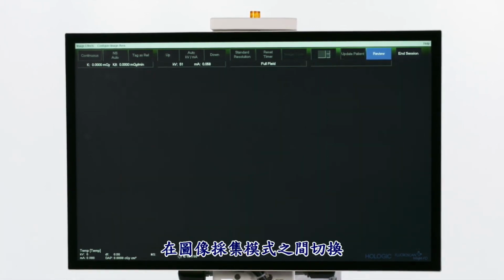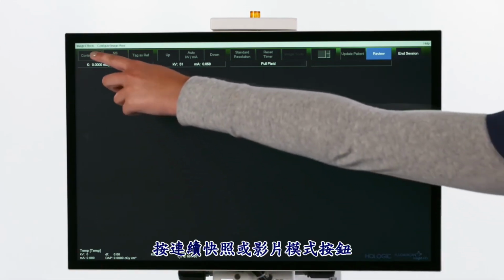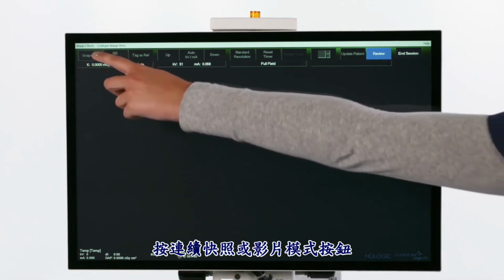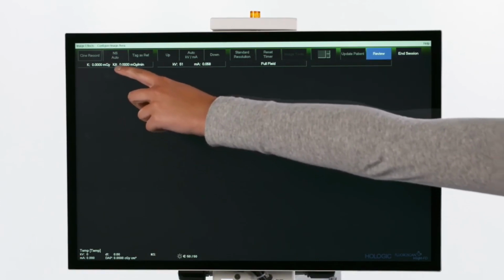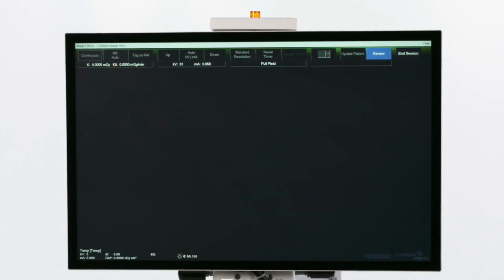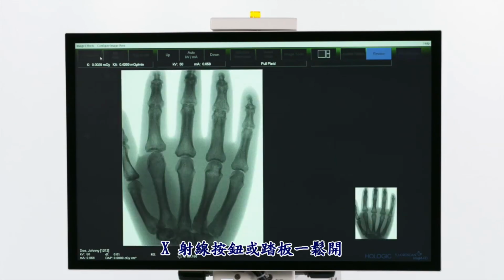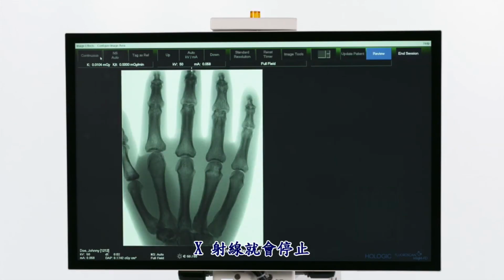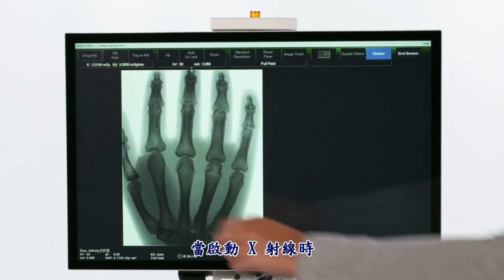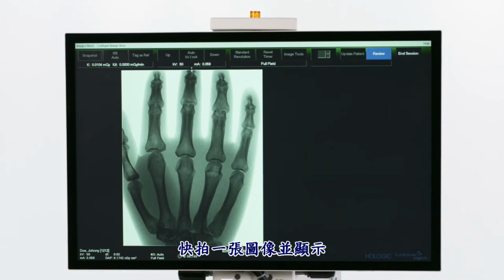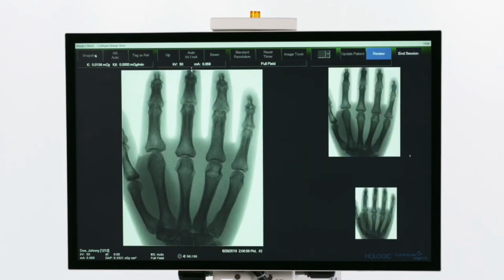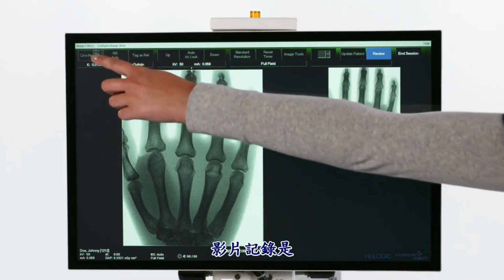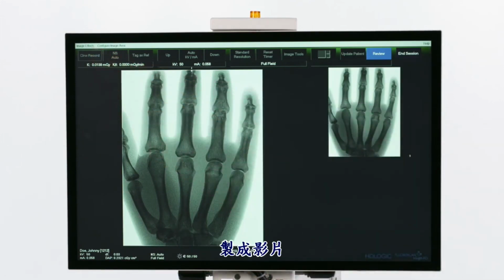To toggle between the image acquisition modes, press the Continuous, Snapshot, or Cine Mode button. When acquiring images in continuous mode, X-rays cease as soon as the X-ray button or pedal is released. When in snapshot mode, one image is captured and displayed when the X-rays are actuated. Cine Record gathers all images acquired in a Cine loop.